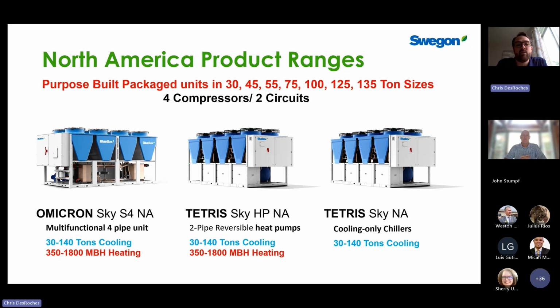And we'll do an example to show why any heat pump that you're using should have the ability to have multiple circuits and defrost them independently to get much higher water temperature stability. So our product offering ranges from 30 all the way up to 135 tons in a single machine, with controls to coordinate the control and staging of all the compressors in a system with up to 32 units. So this means we can do systems up to 4,000 tons.